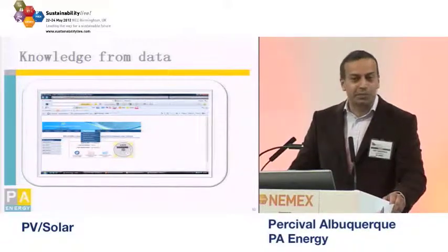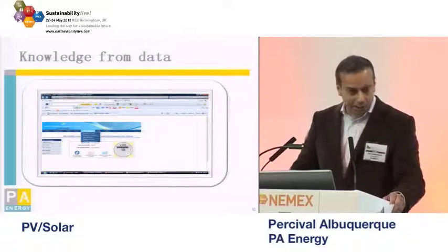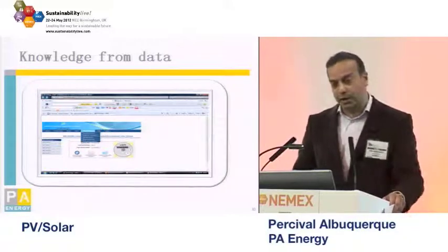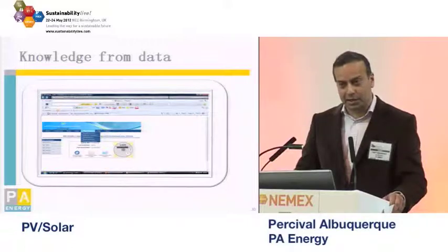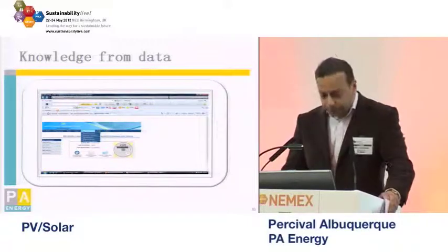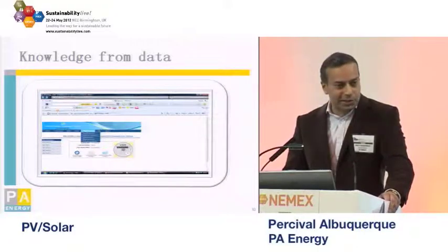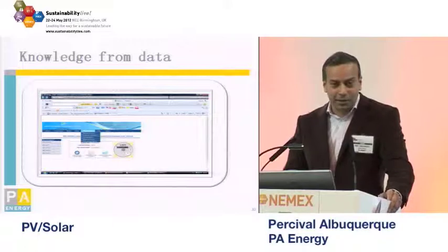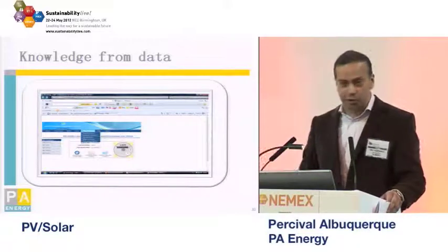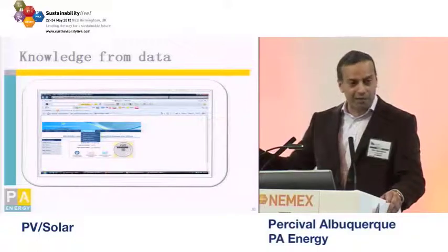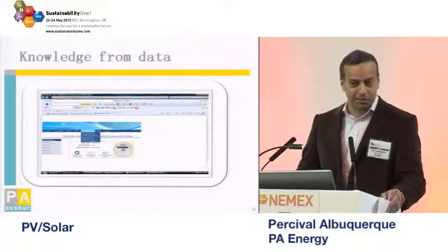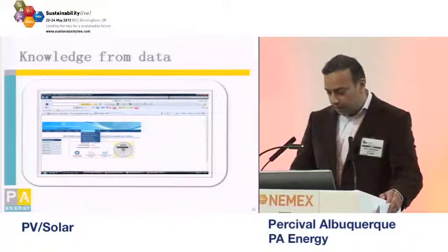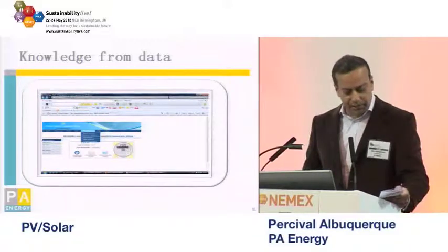So we reported it back to the customer, and then about a year later, they asked us to go and remotely monitor the particular site, which we did. And when we went there a year later to do the installation, the meter readings were still the same. So they actually lost the entire summer because they didn't know. There was too much going on. The individuals occupying the building didn't really have a relationship with that PV system, because that's how it was. So that's the kind of information that can be derived.